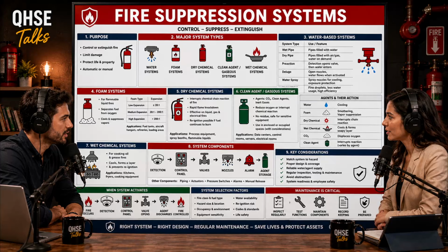Yes. When a fire starts below, the hot gases rise and heat the glass bulb. As the glycerin solution heats up, it expands. And it compresses that tiny air bubble. Right. Once the air bubble is fully compressed, the expanding liquid has nowhere else to go. The internal pressure shatters the glass bulb. With the bulb gone, the plug drops out and the pressurized water hits a deflector plate, spraying over the fire. That is incredibly elegant physics. Yeah. Just fluid expansion, breaking glass.